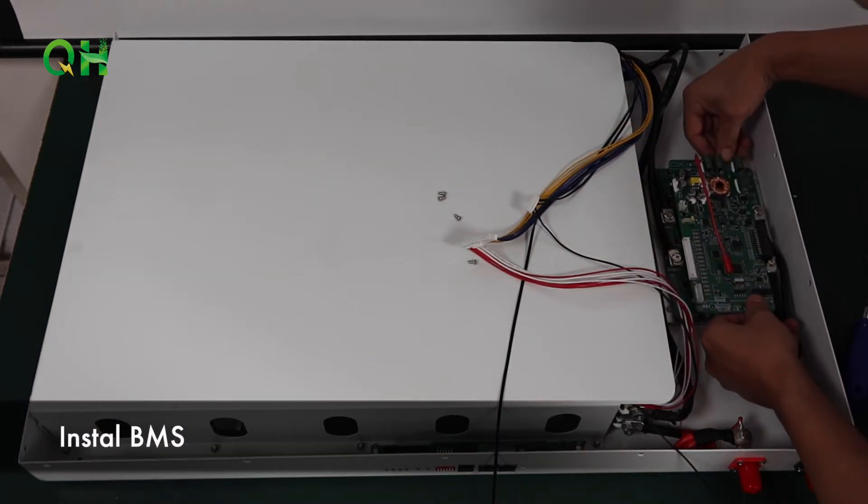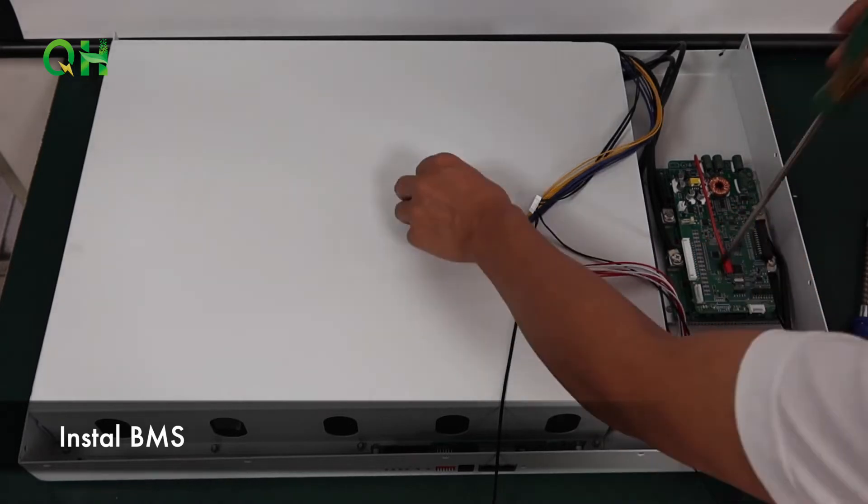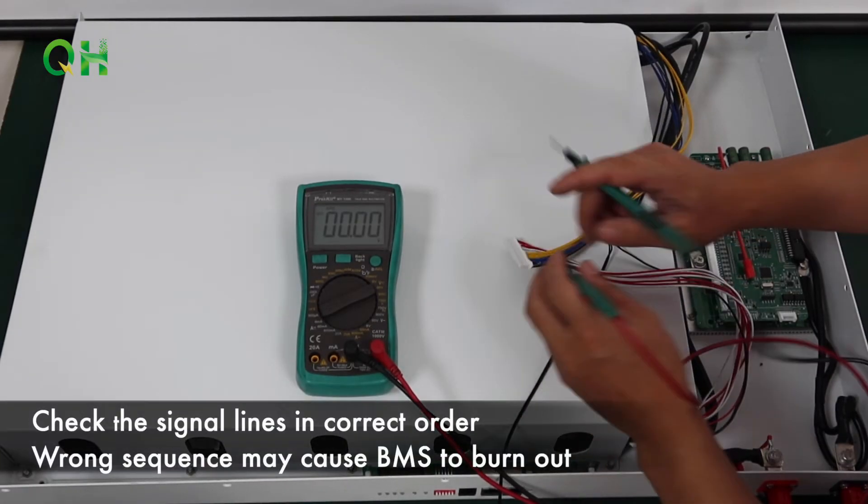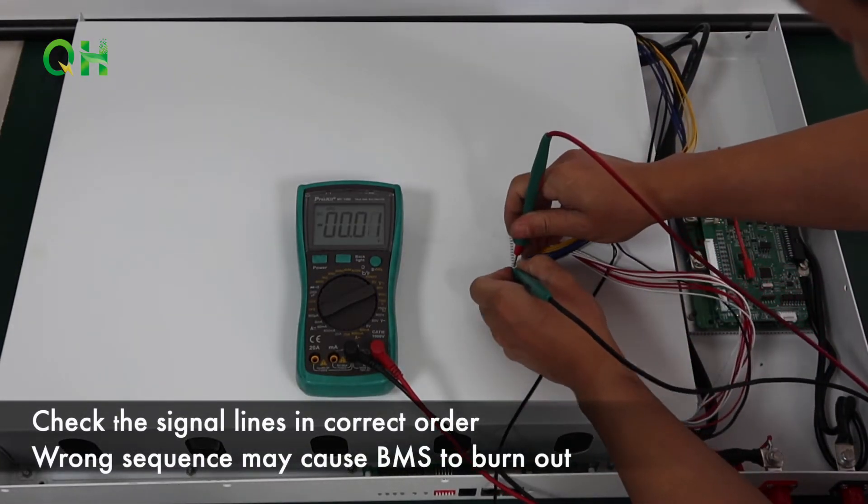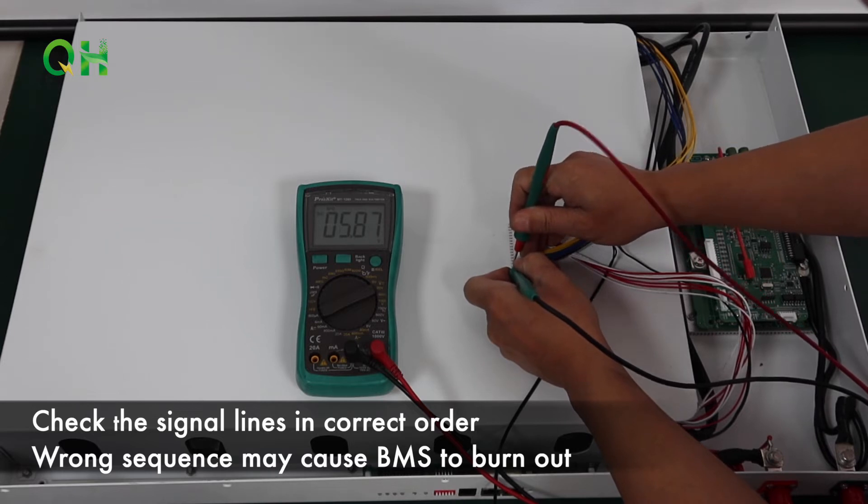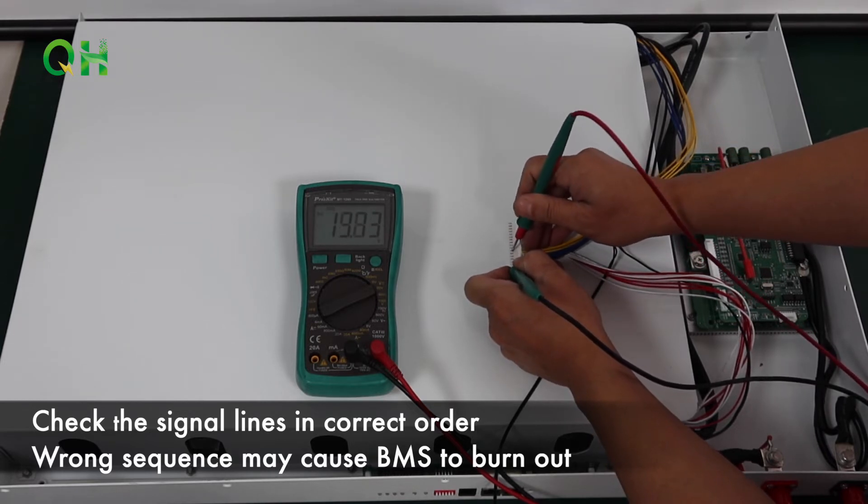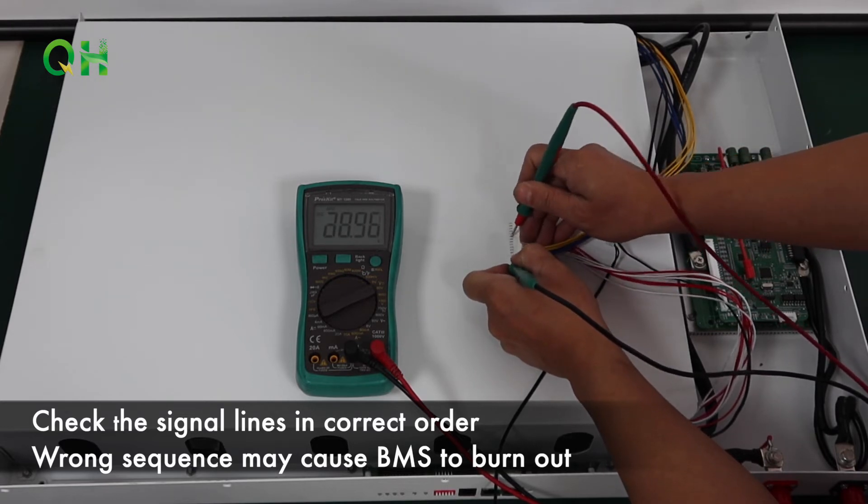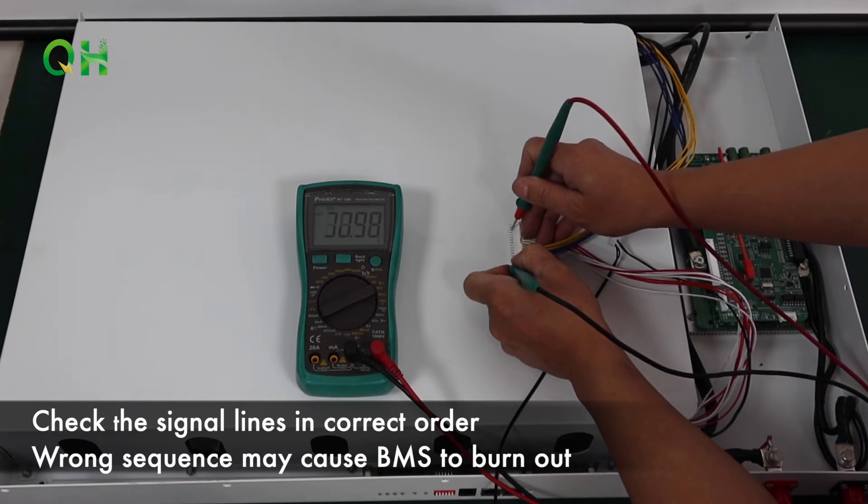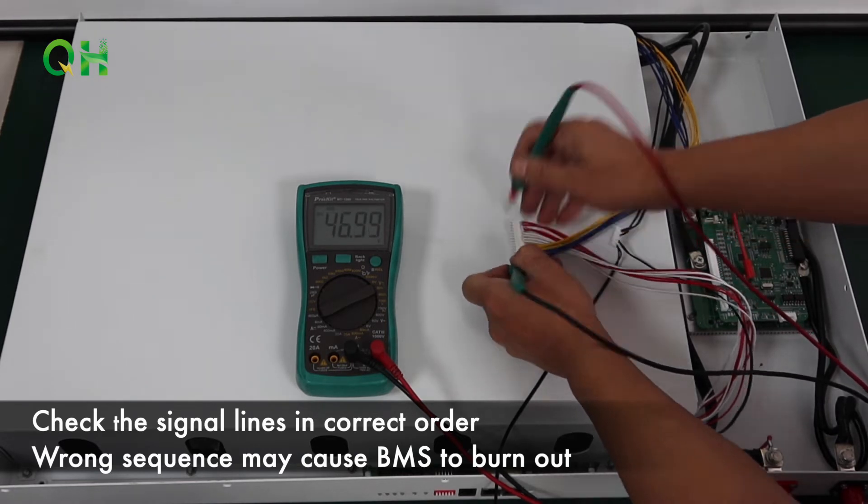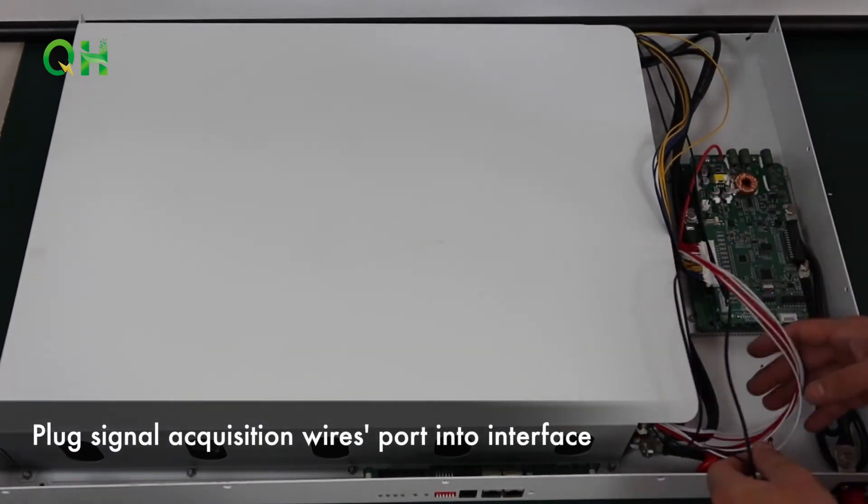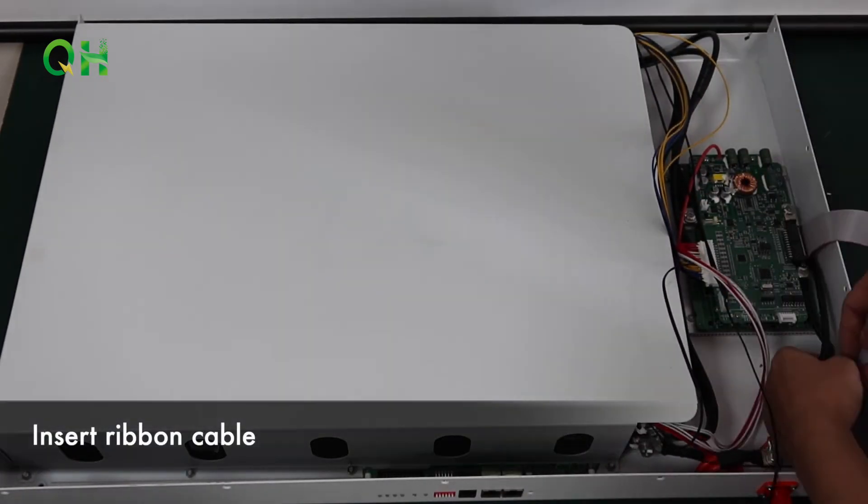Install BMS. Check the signal lines in correct order. Wrong sequence may cause BMS to burn out. Fix the temperature measuring probe near the battery pack. Plug signal acquisition wire support into interface. Insert ribbon cable.